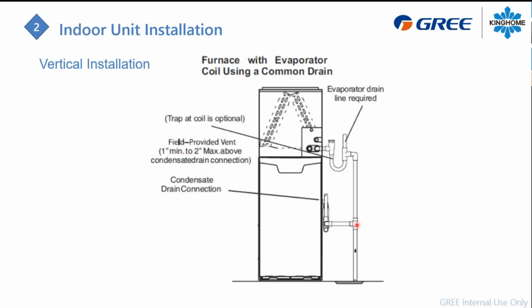But sometimes when you join the drains together, you need to have a proper vent here to make sure you will not push high pressure ventilation back through your furnace's drain, because that can cause you issues with the pressure switch or something else like that. That can cause you some issues in heating with the gas furnace if you always have ventilation pushing into the drain. So make sure you get a vent here to reduce the pressure in the drain pipe, and then you will be good.